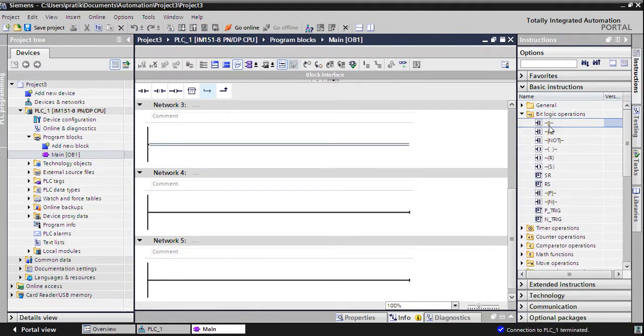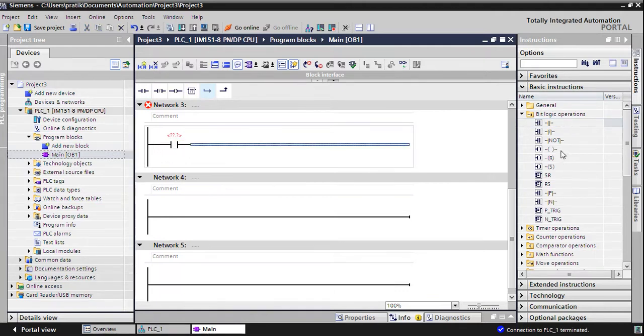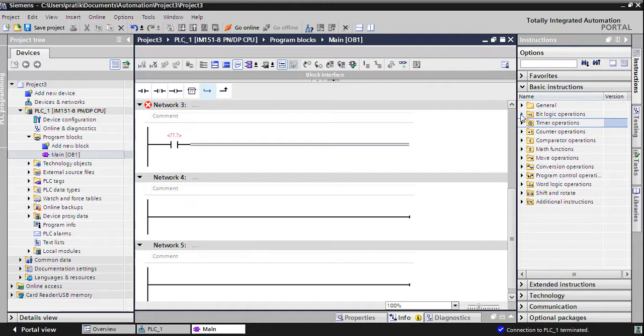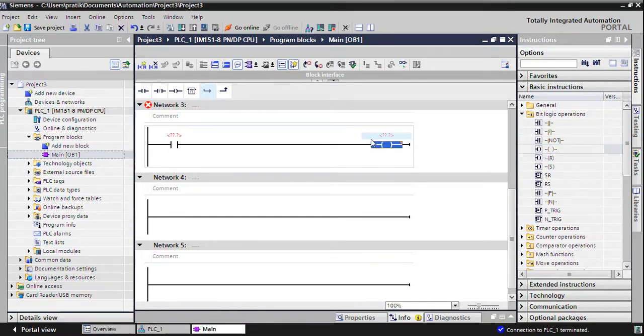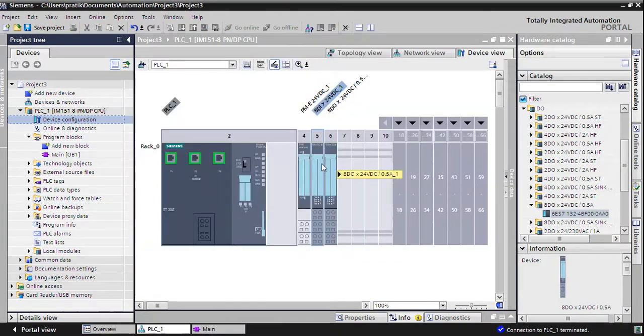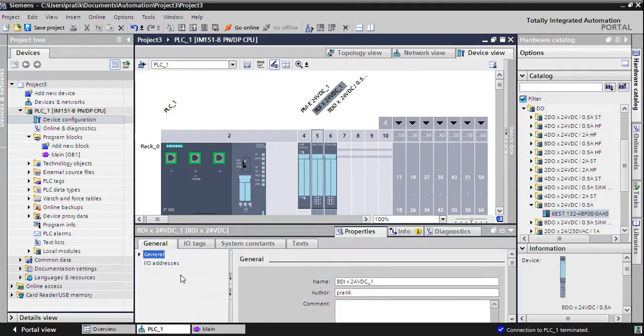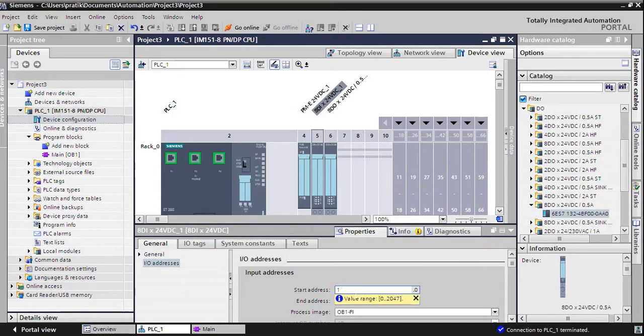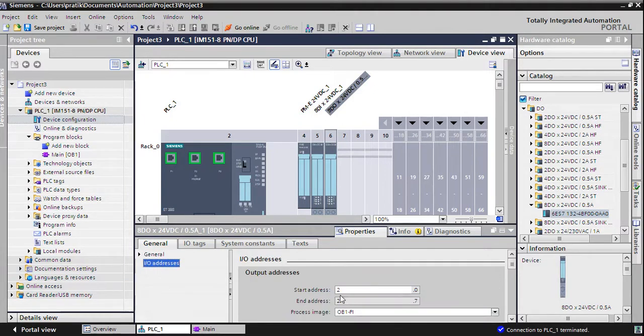I will put a NO contact and an output. For the NO contact I will use input I 0.0, and for the output I will use Q 0.0. I have to configure these two addresses in my DI/DO card as well. For DI I have used I 0.0, so I must give the address 0. For the DO, same thing — I have to use 0.